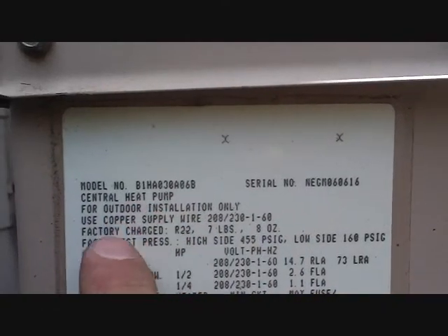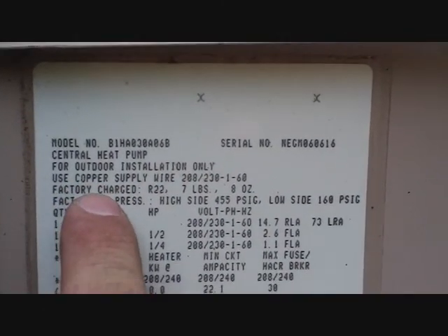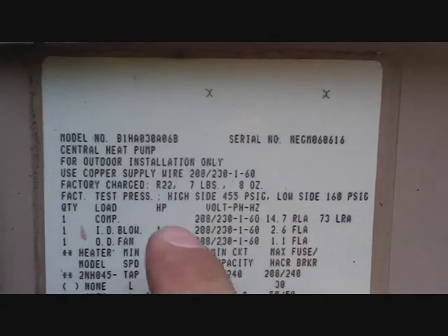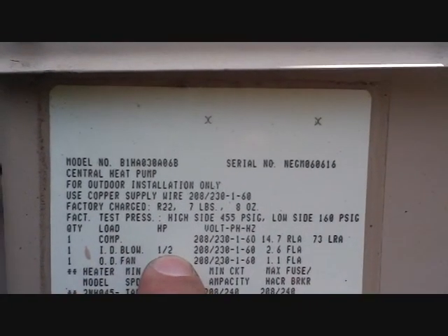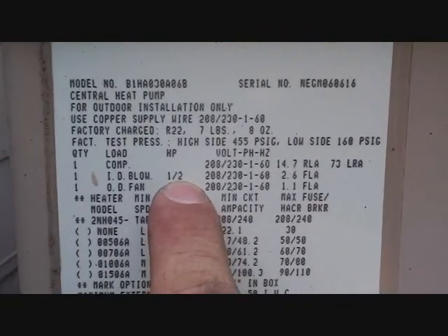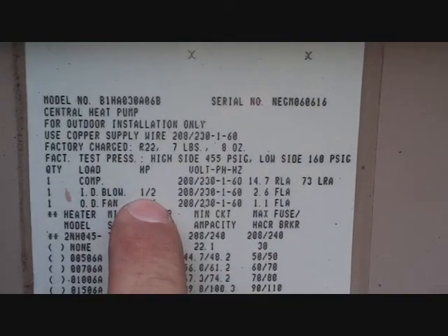Got our data plate here — model number, serial number of the unit. It's a heat pump for outdoor installation only. R22, 7 pounds 8 ounces — that's the factory charge. Indoor blower: 1/2 horsepower — that's where you get the information. Even though it's a Master Fit motor, you had to match up the capacitor to the proper horsepower.